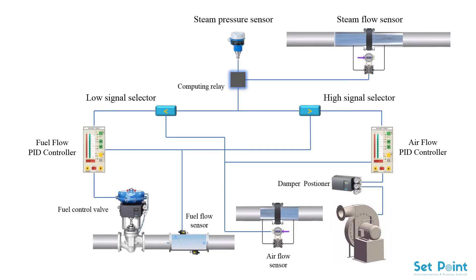Here we have the schematic diagram of the automatic combustion control system used in industrial boilers. This system has four measuring elements: a steam flow sensor to measure the flow rate of steam loaded from the boiler, a steam pressure sensor to measure the pressure of steam in the boiler, a fuel flow sensor to measure fuel flow to the boiler burners, and an air flow sensor to measure the air flow to the boiler.